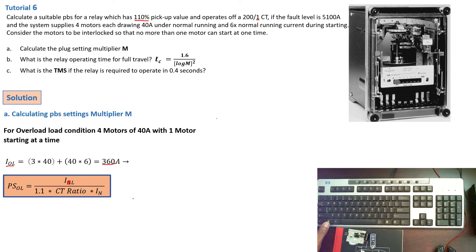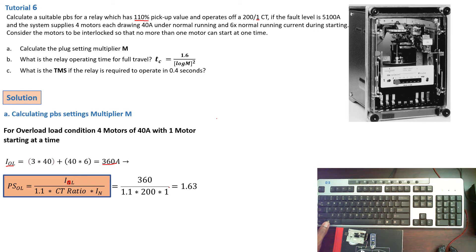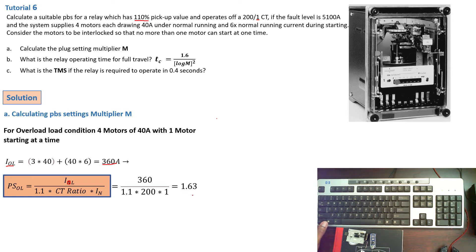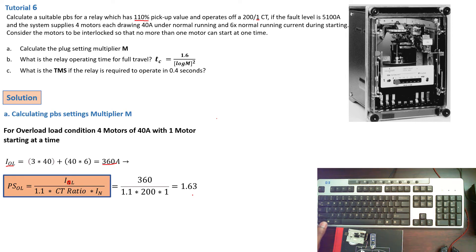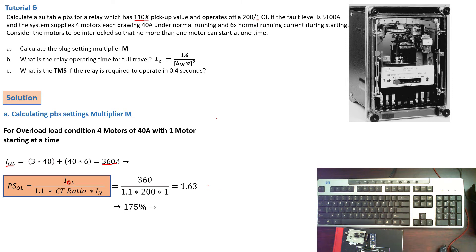Now from here, we can just go ahead and replace the value. 360 over 1.1 times 200 times 1. So that gives us a value of 1.63.